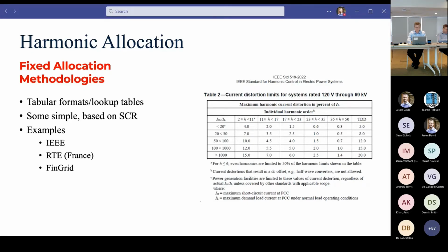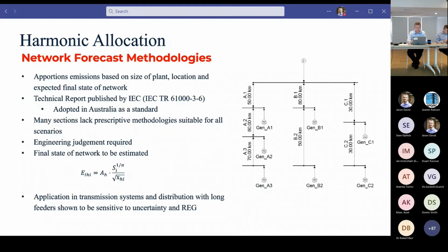As mentioned, the assumptions that feed into this sort of approach and fixed allocation methodologies make the process quite limiting. We reviewed the process on a number of Australian networks and looked at how the IEEE 519 approach actually performs. What we find is that it is very limited in its capability, particularly in networks with any level of resonance or long feeders. It really starts to struggle, and ultimately results in your planning levels being exceeded.